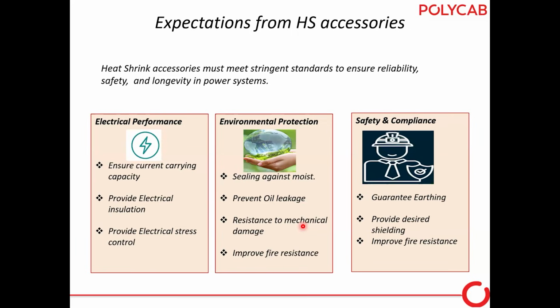Second, even though we connect two cables, we require an environmental protection system also. Sealing against moisture ingress has to be there. If there is a PILC type of cable, oil leakage should not travel from one side to the other. Then resistance to mechanical damage, abrasion, and chemicals should not affect the joints, and it should improve fire resistance. In safety and compliance, it should guarantee earthing, provide the desired shielding to the cable, and improve fire resistance also. So any customer who asks for joints or terminations, that is cable accessories, expects these things from the manufacturer or the product.